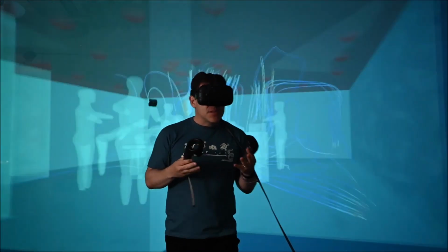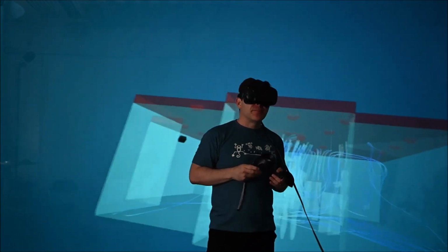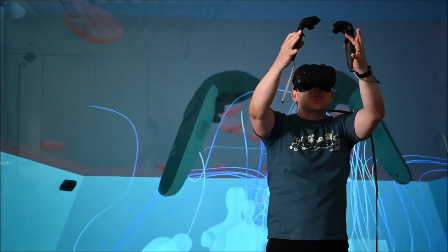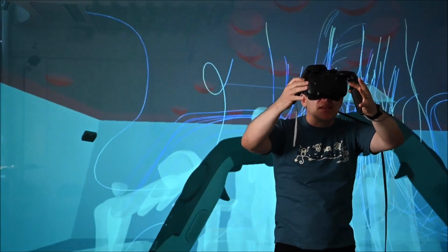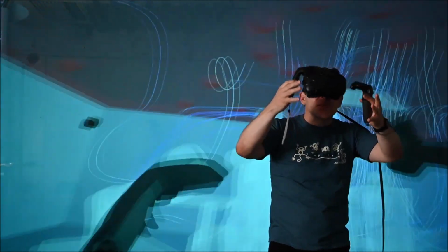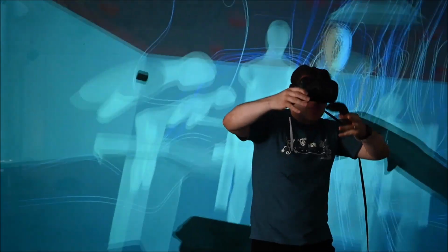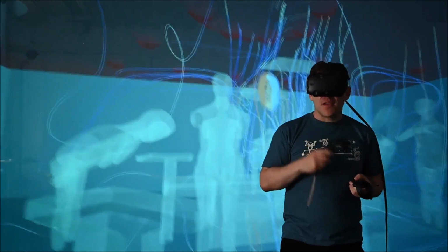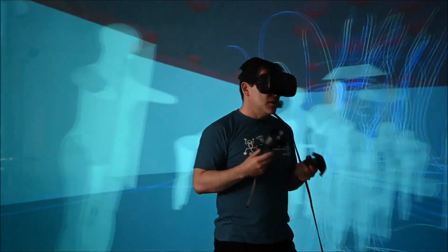Why is that happening? Well, it's not clear, but the visualization allows us to see something that we couldn't see before. Furthermore, as I mentioned, the air flows into the room, and when it comes in, it is very clean air, and it remains clean until vortices pick up particles in the air, and those particles include bacteria and contaminants. So all of these vortices are pushing and pulling and tugging the particles, reducing the quality of the air in the operating room. That's the type of understanding we want to give the people, the stakeholders in the room, doctors and nurses.